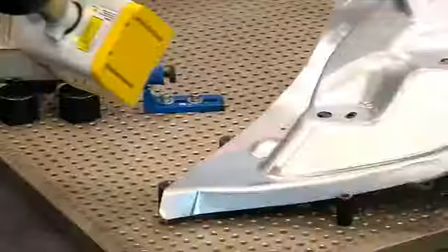When you say it's been built with scanning and so forth in mind, what do you mean by that? Traditionally CMMs use a touch trigger probe, which is good for general inspection and can measure most features. Scanning probes, which are tactile, have come along recently, and they give other benefits for getting a lot of data very quickly from the CMM. But they have limitations in productivity when you come to a complex surface. So the laser scanner gives you much more productivity on a complex surface like this. Because it's faster at collecting the data points. So the three technologies have their own individual benefits, but when you put them together, you extend the scope of the CMM.